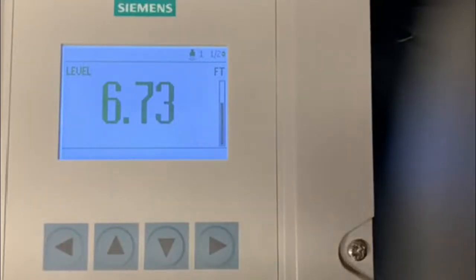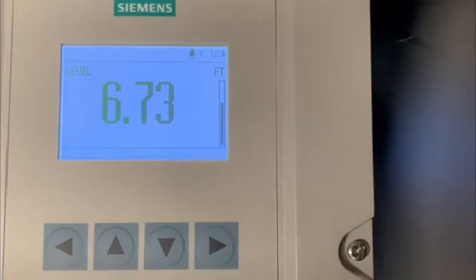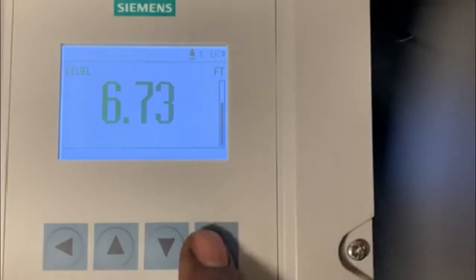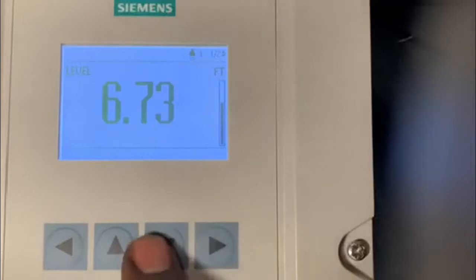Have you ever had a HydroRanger that you thought was not displaying the correct values, or locking in onto false echoes? One of the unique features of the HydroRanger HMI over its predecessors is the new GUI interface allowing you to view any echoes that the transducer would see. To access this, we must first hit the right arrow key.